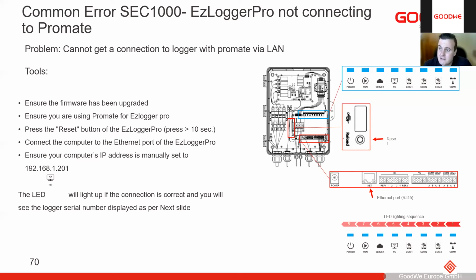And then once we're done configuring this device in ProMate, you can set it back to DHCP, or you can manually press that reset button to reset it back to DHCP and then connect it to the customer's network. If you are only going to use DHCP, you can use that as well, especially if you only have a small network or a small dedicated router. You know, there's not a lot of devices. Then you can just plug it straight into a router. You'll automatically get an IP address that you can just type into ProMate and connect to it.